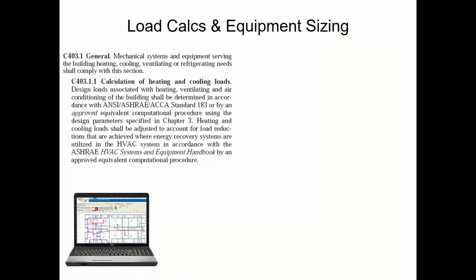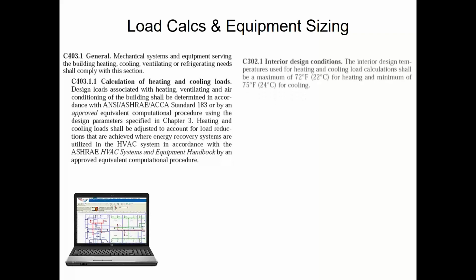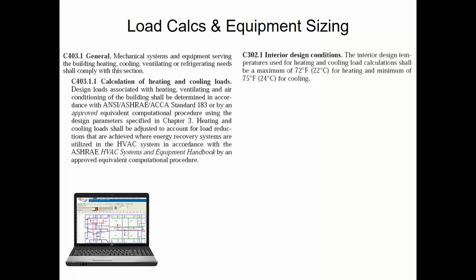Load calcs are not optional. You're required to do these by energy code. So every one of you that's on this call, I believe when I looked at the list, everybody's from a state that has an energy code. Everybody has to do this. It's not an optional thing. Every time you put in a new piece of equipment, you have to do a proper load calculation. The code dictates the indoor temperatures. At most, you can design it to heat for 72. You can do less. You can design it to only heat your building to 70, but at most 72. And cooling, the lowest temperature you're allowed to design the cooling for by law is 75 degrees. There is no code in any state that allows you to design cooling to go below 75 degrees.